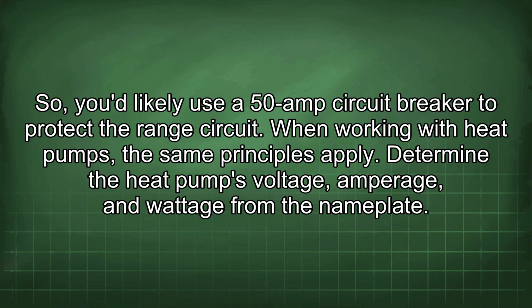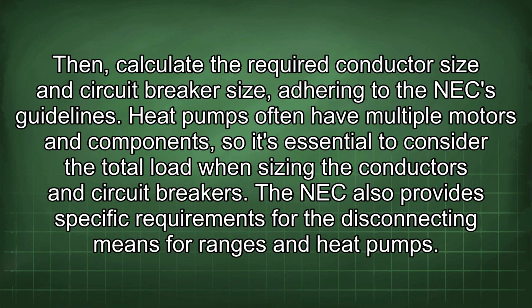When working with heat pumps, the same principles apply. Determine the heat pump's voltage, amperage, and wattage from the nameplate. Then calculate the required conductor size and circuit breaker size, adhering to the NEC guidelines. Heat pumps often have multiple motors and components, so it's essential to consider the total load when sizing the conductors and circuit breakers. The NEC also provides specific requirements for the disconnecting means for ranges and heat pumps.